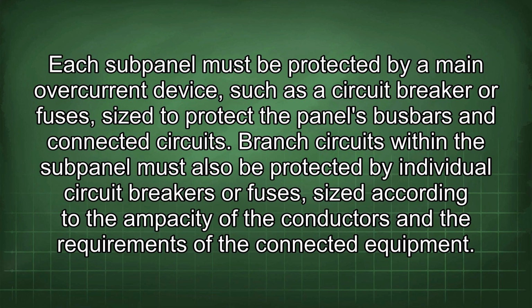Fifthly, consider overcurrent protection. Each subpanel must be protected by a main overcurrent device, such as a circuit breaker or fuses, sized to protect the panel's busbars and connected circuits. Branch circuits within the subpanel must also be protected by individual circuit breakers or fuses, sized according to the ampacity of the conductors and the requirements of the connected equipment.